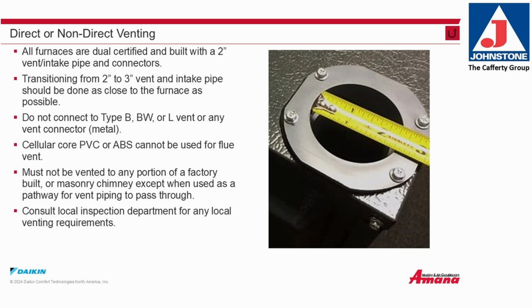Venting. Direct or non-direct venting. All furnaces are dual certified and built with a 2-inch vent intake pipe and connectors. Transitioning from 2-inch to 3-inch vent and intake pipe should be done as close to the furnace as possible. Do not connect type B, BW, or L vent or any vent connector that's metal. Cellular core PVC or ABS cannot be used for flue vent.